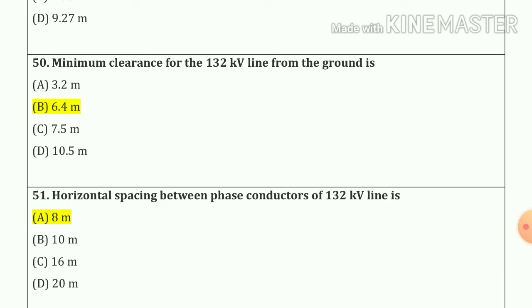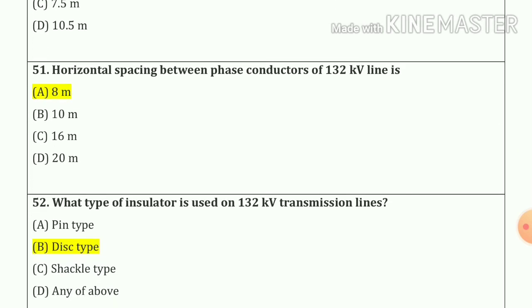Question number 50: minimum clearance for the 132 kV line from the ground is 6.4 meters — option number B. Question number 51: horizontal spacing between phase conductors of a 132 kV line is 8 meters — option number A.